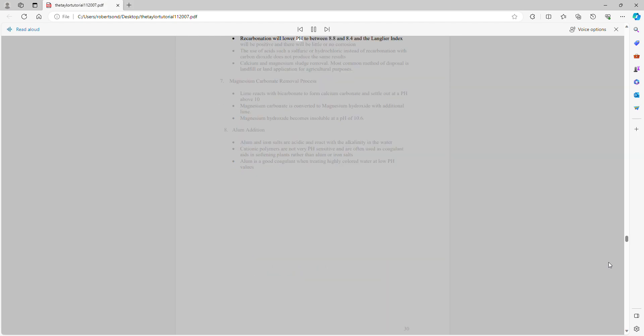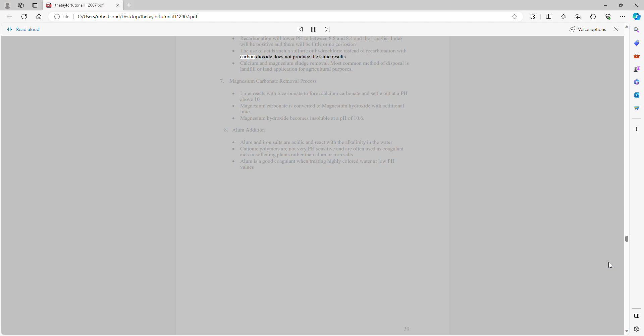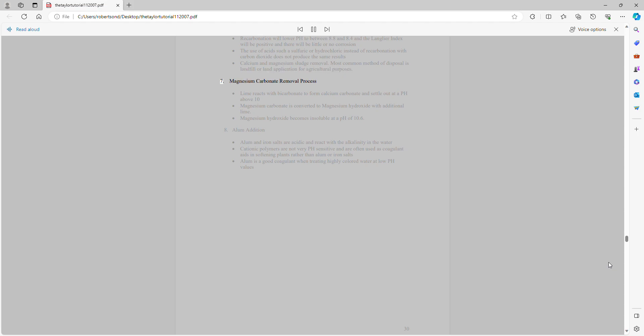Recarbonation will lower pH to between 8.8 and 8.4, the Langelier index will be positive, and there will be little or no corrosion. The use of acids such as sulfuric or hydrochloric instead of recarbonation with carbon dioxide does not produce the same results. Calcium and magnesium sludge removal: the most common method of disposal is landfill or land application for agricultural purposes.